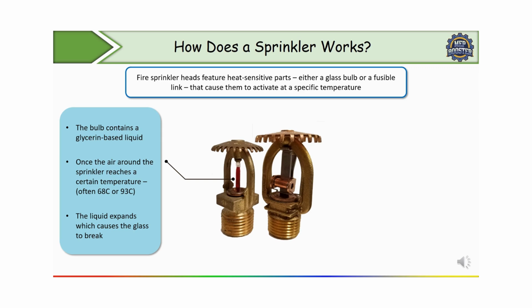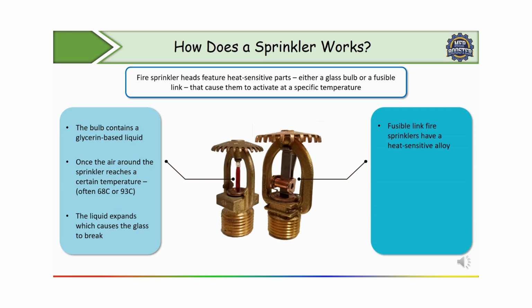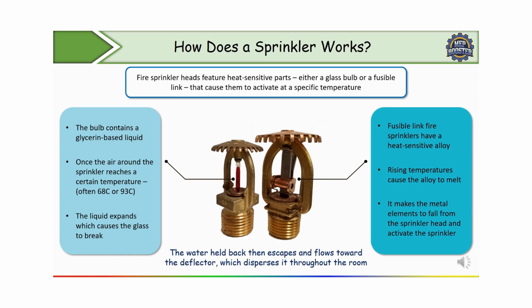Correct? In the same way, with the fusible link, this type of fire sprinkler has a heat sensitive alloy. Rising temperature causes the alloy to melt. It makes the metal element fall from the sprinkler head and activates the sprinkler. So the water held back then escapes and flows towards the deflector, which disperses it throughout the room. So in this way the fire sprinkler works.